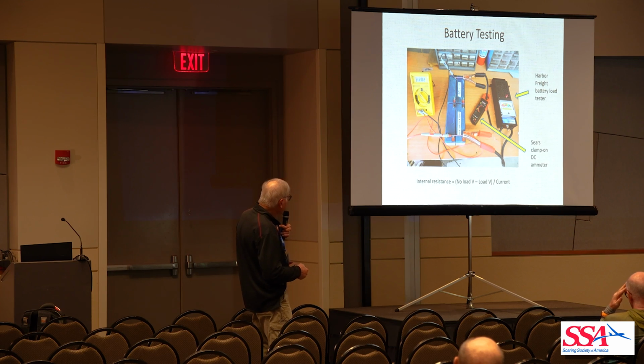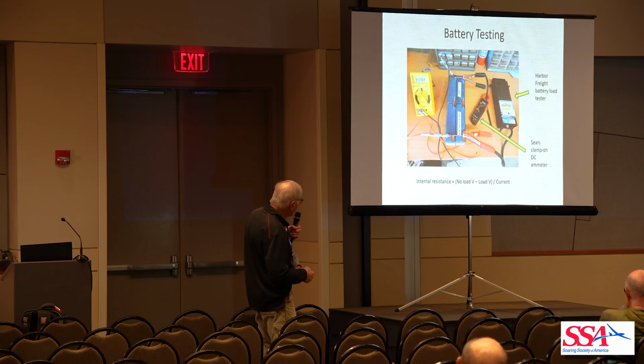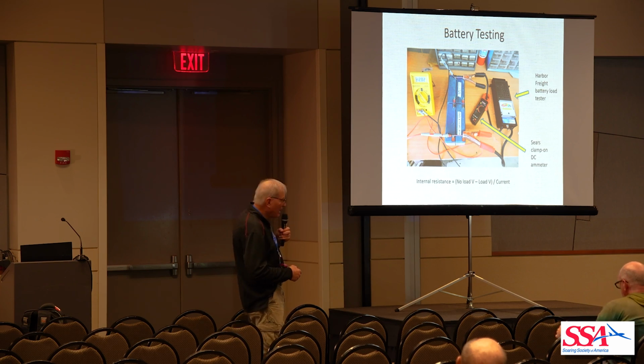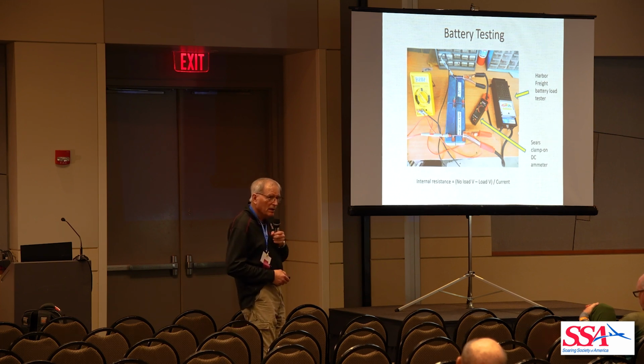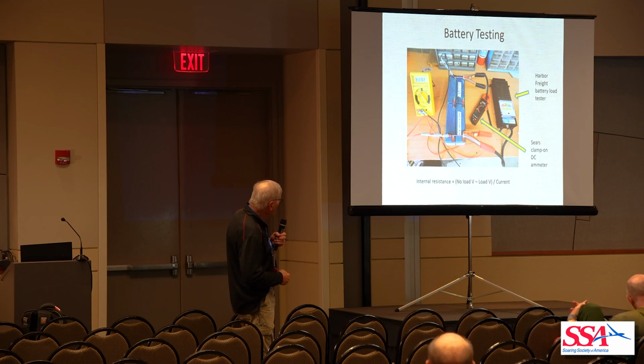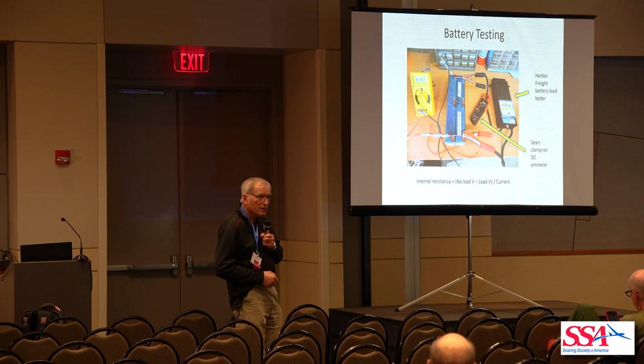This is a battery load tester from Harbor Freight. It has a voltmeter on there, and it switches in roughly a 100 amp load. I measured it here this last week, and it was actually like 84 amps. And then I've got a clamp-on DC ammeter. If you don't have a clamp-on DC ammeter, buy one, because they're really handy devices for troubleshooting DC systems. They just clamp around the wire and show you the DC current.